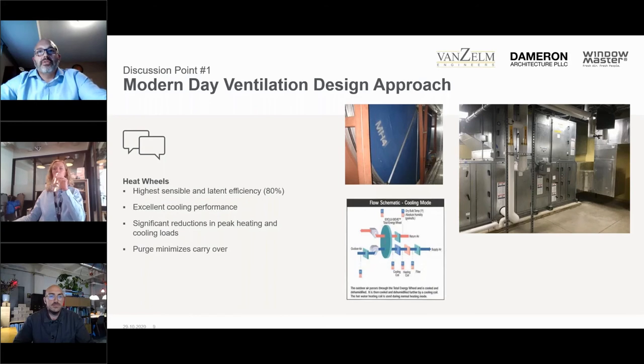And this just shows a little bit about when you're looking at those DOAS systems, we want to do what we can to minimize energy use. So we utilize heat recovery wherever possible. And one of the most effective means of heat recovery, when your exhaust stream doesn't have any particulates or smells, is to use a heat wheel. And you can get a minimum of 80% efficiency there. So it's taking in what you're bringing in for outside air, preconditioning it through the use of the energy wheel, and it's cutting down on your energy impacts to deliver the ventilation air to the space for temperature control.